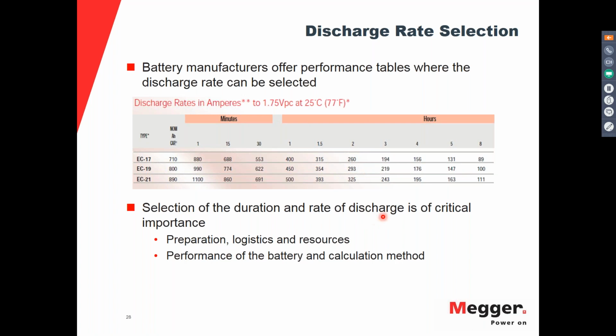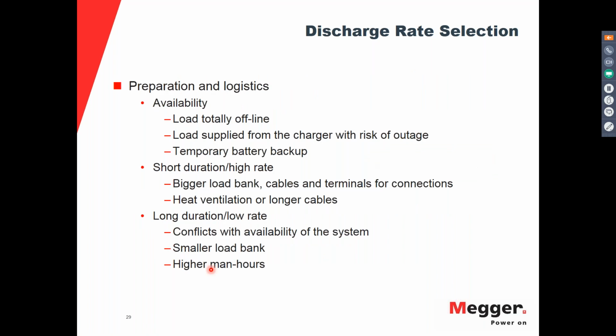As again, very important, you need to look for a duration that includes or envelopes the duration of the duty cycle. And this will define your preparation, your logistics, and resources. If you select a very high rate, this means that you need a very big bank, and remember that that is also going to affect your result. Higher rates will mean less efficiency of the battery.